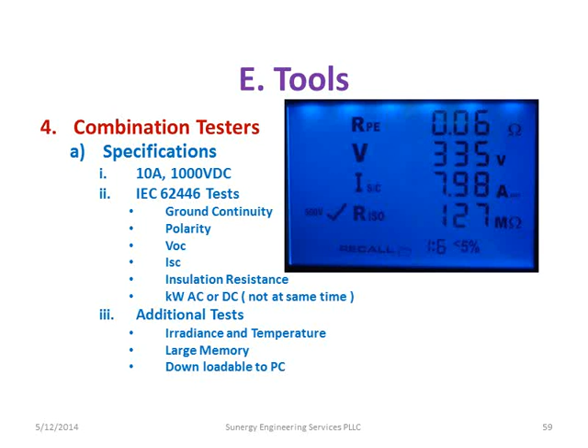So the Seaward, that's this guy right here. You guys can come up and take a look at this stuff afterwards too. It's about $1,600, and it comes with an irradiance meter and a temperature probe that you can put onto the cells, and it's radio controlled. So it sends that information back to the meter so you can just do the test right down in the combiner box at the array. And it also has an optional clamp on so that you can actually do the kilowatts of DC going into the system.